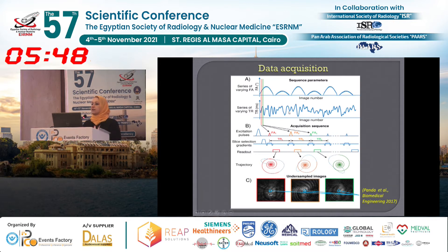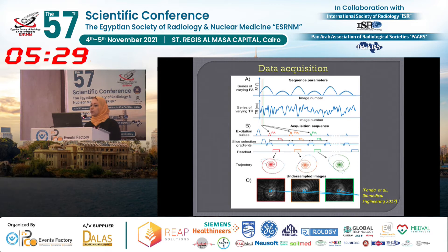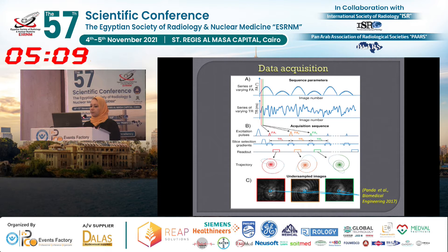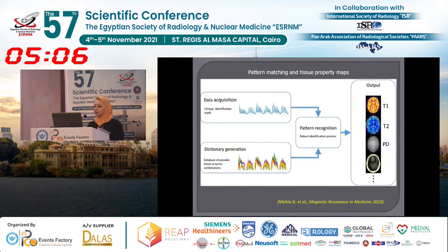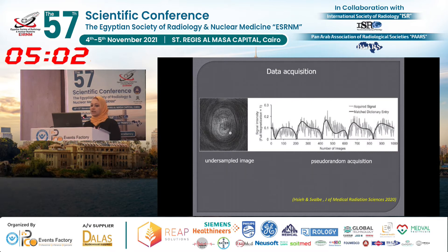Regarding data acquisition, there is a fundamental difference between MRF and conventional MRI in the way data is acquired. Instead of repeating the same single acquisition parameter over time in a specific sequence while keeping all other parameters consistent — which is the case in conventional MRI — in MRF, multiple acquisition parameters such as flip angle and repetition time are varied across the acquisition in a pseudorandom manner, in order to obtain unique signal time courses or fingerprints specific for each tissue type.